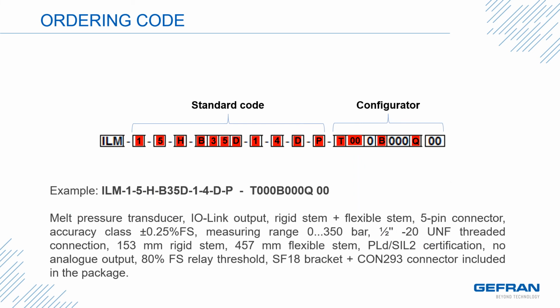Now shown is the complete code based on the selections observed in the previous slides. What this means is a melt pressure transducer with I/O link output, rigid stem, and a flex stem of certain lengths described by the digits, a 5-pin connector with accuracy class of 0.25% of full scale. The measuring range is 0 to 350 bar. The rigid stem thread is 1/2-20 UNF. The rigid stem length is 153 millimeters or 6 inches. The flexible stem length is 457 millimeters or 18 inches.